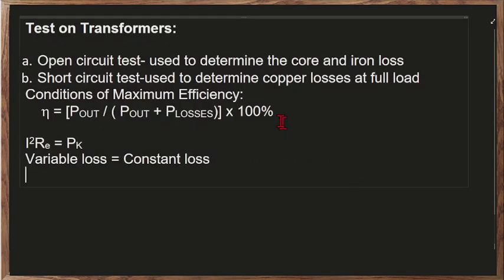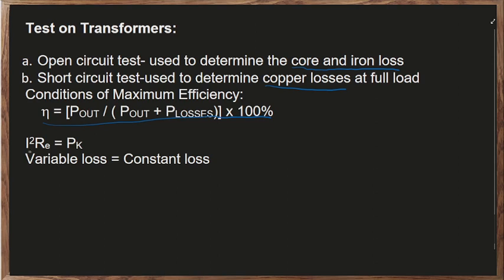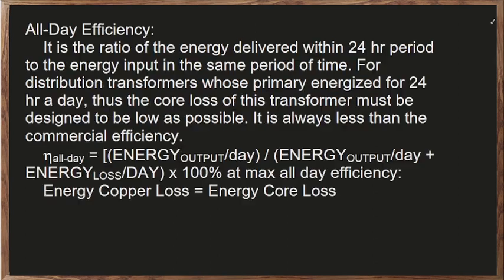Okay, so tests on transformer. First we have the open circuit test, used to determine the core and iron loss, or the fixed losses, no? When we go to the short circuit test, it is used to determine the copper losses at full load. This is the formula for efficiency, and this is the formula for the copper loss. So the variable loss can also be equal to the constant loss, no?